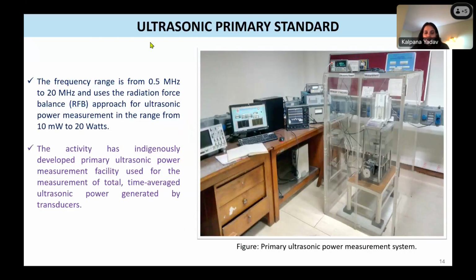This picture is from CSIR NPL, where I did my PhD. This is the primary ultrasonic power measurement system, used for calibrating ultrasonic power, that is, how much power a transducer is going to emit. The activity has an indigenously developed primary ultrasonic power measurement facility, used for the measurement of total time-averaged ultrasonic power generated by the transducer. The frequency range is 0.5 megahertz to 20 megahertz, and it uses the radiation force balance principle.